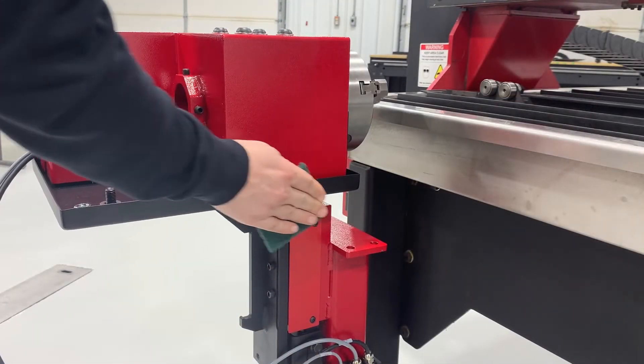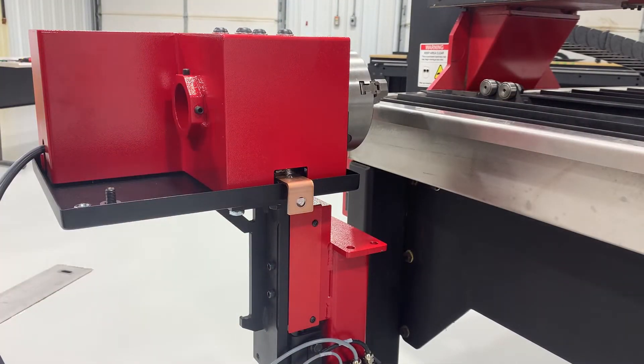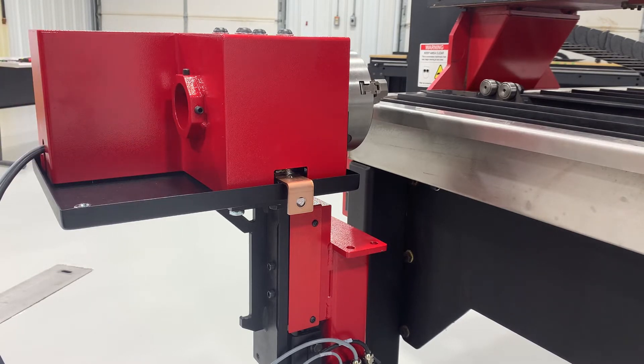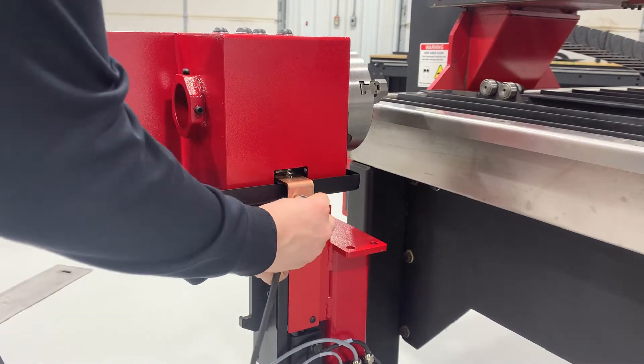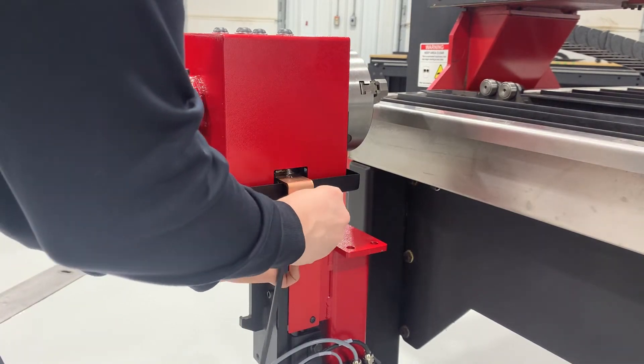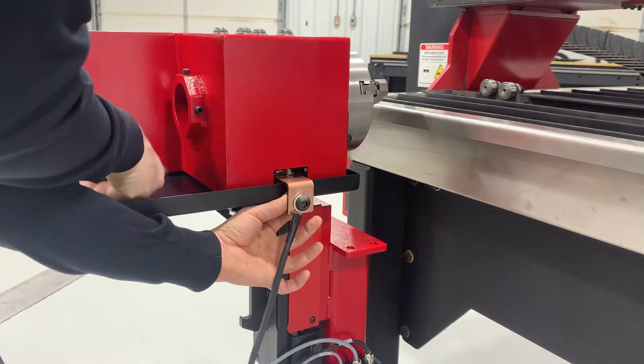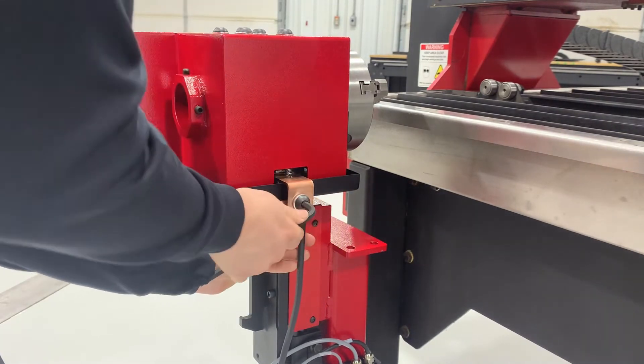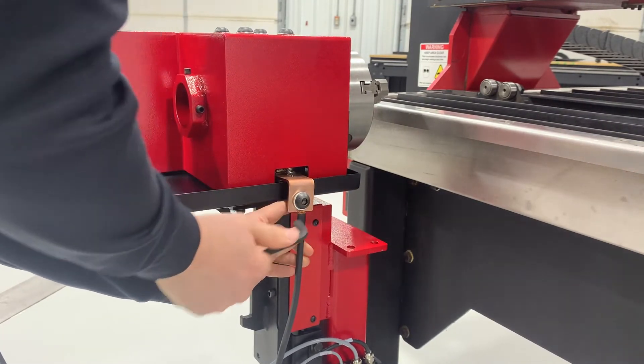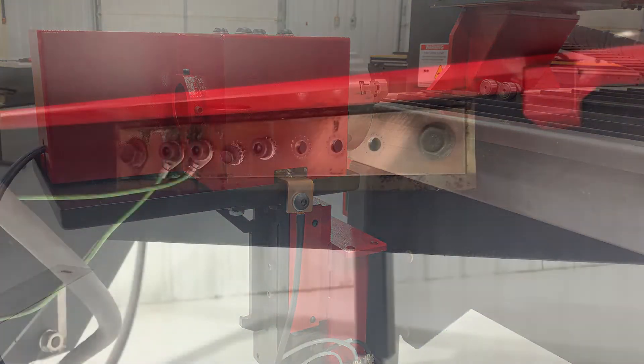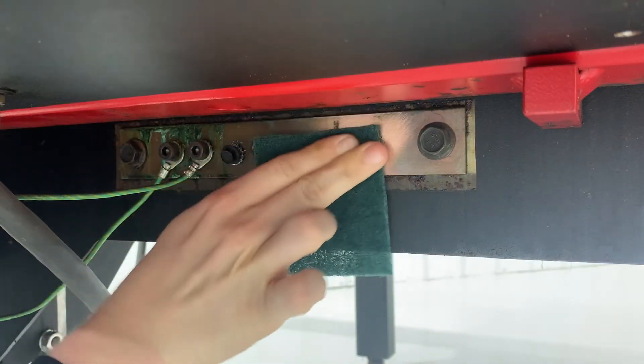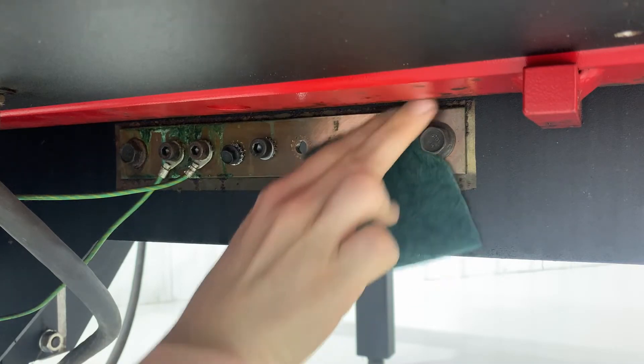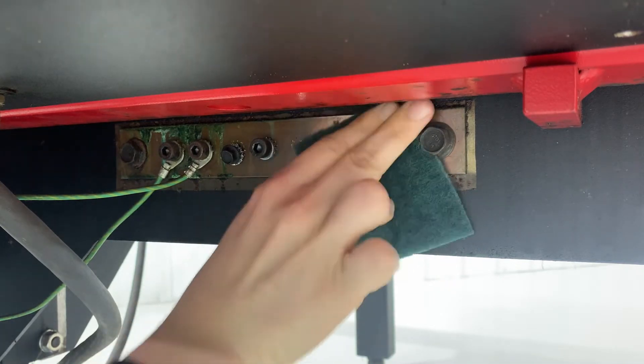Next we're going to connect the work lead to the rotary axis copper bar. Anytime we're making a connection to copper we want to make sure that we buff it first with a pad or fine grit sandpaper just to get rid of any corrosion that might be there and impede the current's path. With plasma it's really important that we make sure that the current flows where we want it to go and it doesn't find its way back through the control cables into the panel. Here's the final connection of the work lead back to the machine's bonding bar.